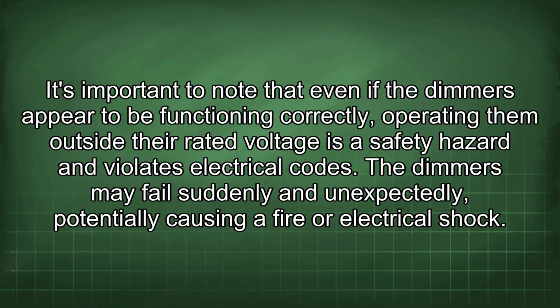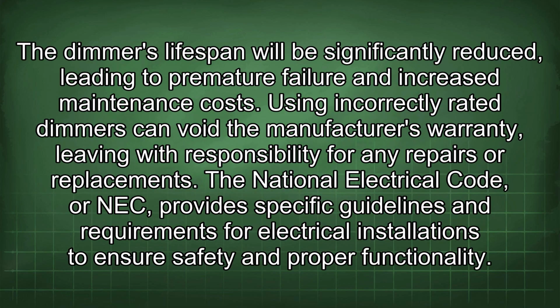It's important to note that even if the dimmers appear to be functioning correctly, operating them outside their rated voltage is a safety hazard and violates electrical codes. The dimmers may fail suddenly and unexpectedly, potentially causing a fire or electrical shock. The dimmer's lifespan will be significantly reduced, leading to premature failure and increased maintenance costs. Using incorrectly rated dimmers can void the manufacturer's warranty, leaving you with responsibility for any repairs or replacement.